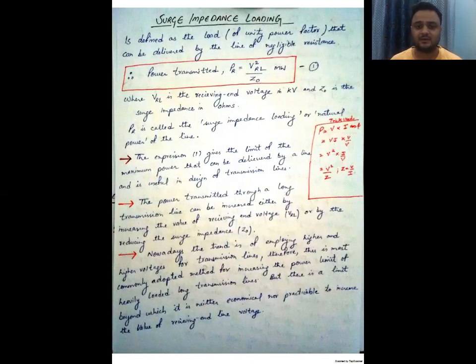How much power can be delivered to meet that load through a transmission line is given by the formula: power transmitted equals V square RL divided by Z0, in megawatts, where VRL is the receiving end voltage in kilovolts and Z0 is the surge impedance in ohms.